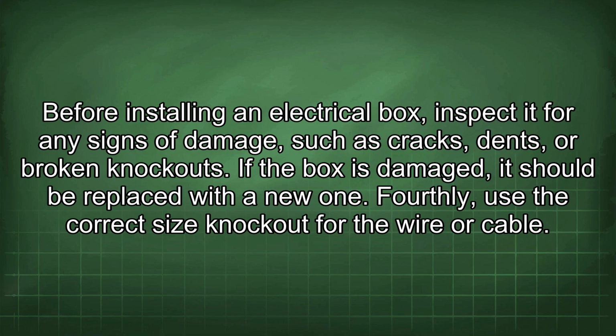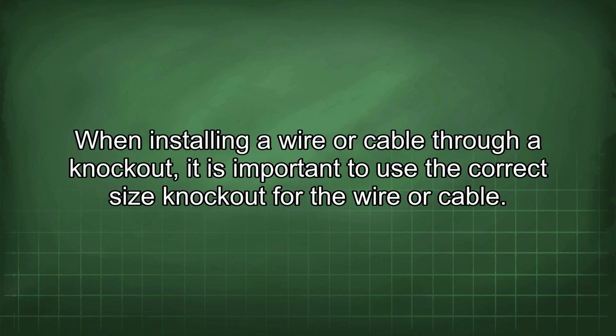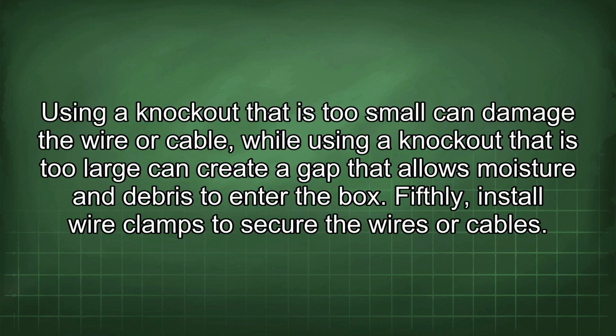Fourthly, use the correct size knockout for the wire or cable. When installing a wire or cable through a knockout, it is important to use the correct size knockout for the wire or cable. Using a knockout that is too small can damage the wire or cable, while using a knockout that is too large can create a gap that allows moisture and debris to enter the box.